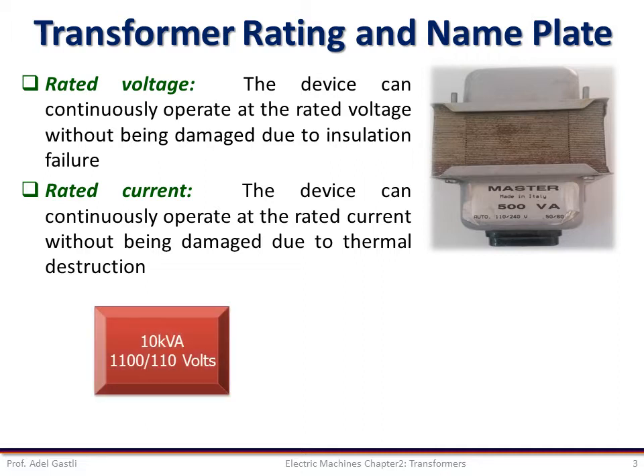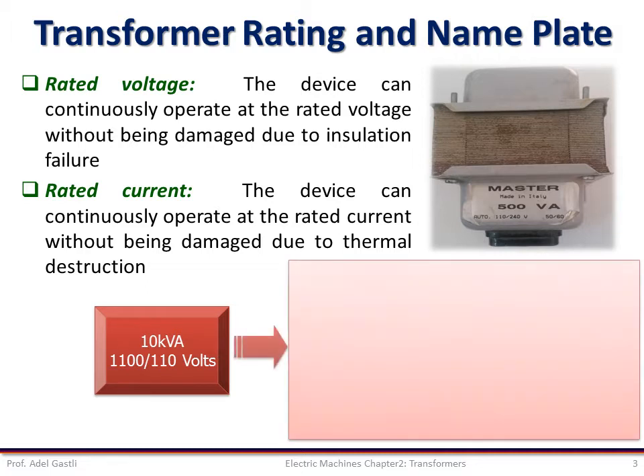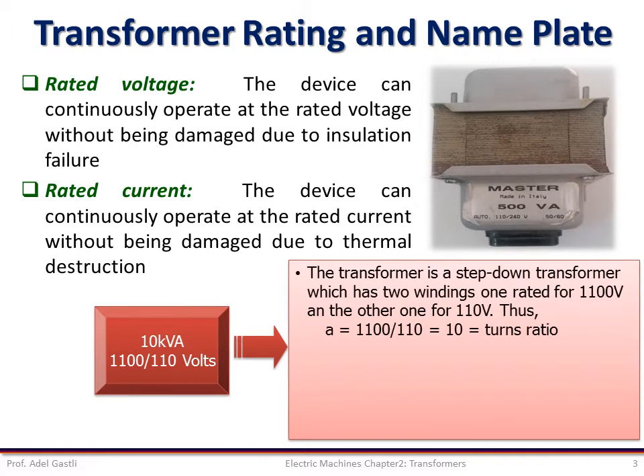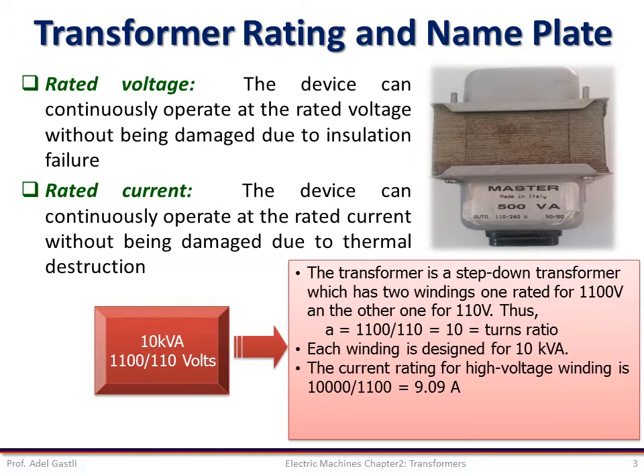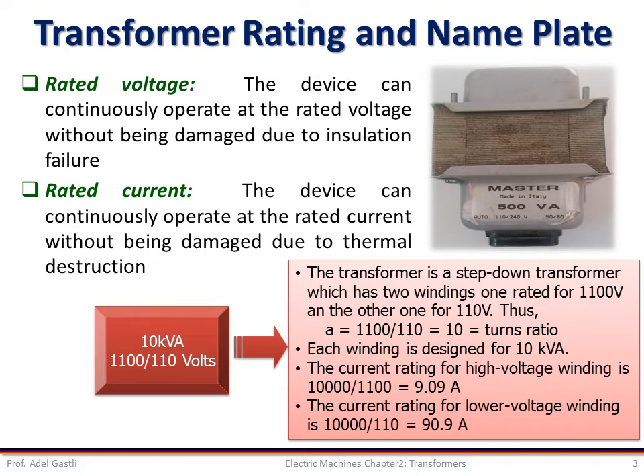For instance, if a transformer has the following information written on its nameplate, then we can deduce that the transformer is a step-down transformer which has two windings, one rated for 1100V and the other for 110V. Thus, the turn ratio A is equal to 1100 divided by 110, which is 10. This means also that each winding is designed for a maximum power of 10 kVA. We can deduce the current rating for the high voltage winding as 10,000 over 1100, which is 9.09 amps, and the current rating for the lower voltage winding is 10,000 divided by 110, which is 90.9 amps.